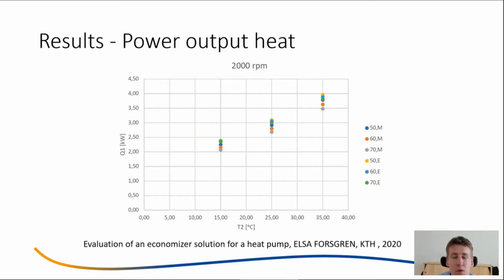So how is this working then? If we are running the machine at 2000 revolutions per minute, I should explain what the different things are here. On the x-axis, we have the evaporation temperature. We are measuring here 15, 25, and 35 degrees. The different colors are different condensation temperatures: 50, 60, and 70. The denotation M is measured values and E is estimated or theoretical values. We can see that the theoretical values match the measured values pretty well, and the heat power output we get is between 2 and 3 or 4, something like that, when we run the compressor at 2000 RPM.